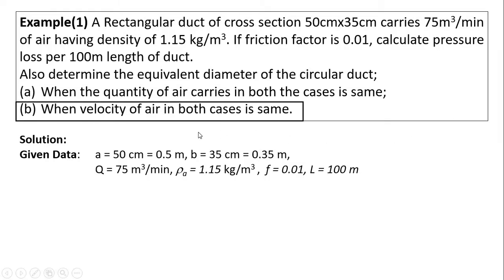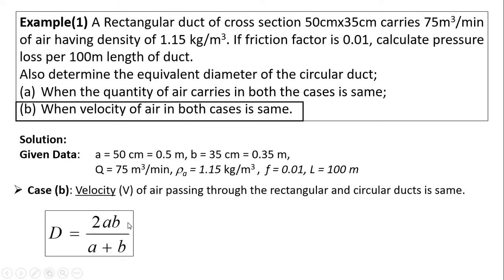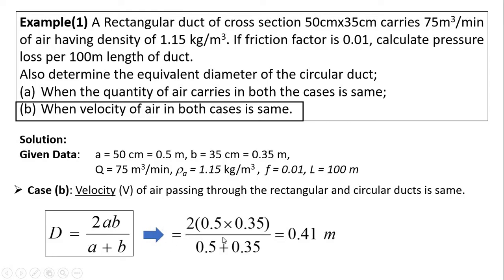For the second criteria — when velocity of air in both cases is the same — we use the second formula for equivalent diameter of circular duct. By putting values of a and b, we get equivalent diameter D = 0.41 m. So in this way we can calculate the equivalent diameter of circular duct for a given rectangular duct.